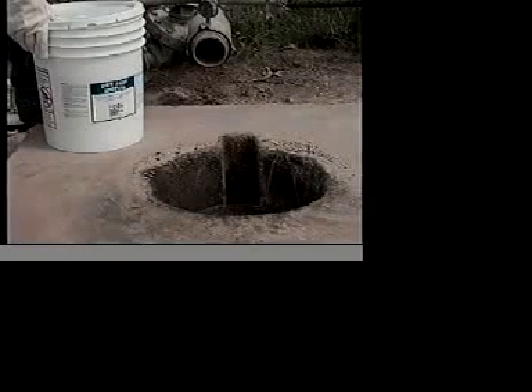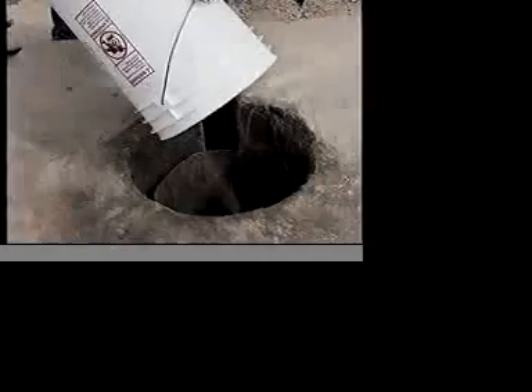This well in Terry County, Texas was plugged with rust and hard water scale, producing only 300 gallons or 1,135 liters per minute. It was treated with Cody Chemical's Dry Acid Special, scrubbed with a wire brush, and now produces 900 gallons or 3,400 liters per minute.